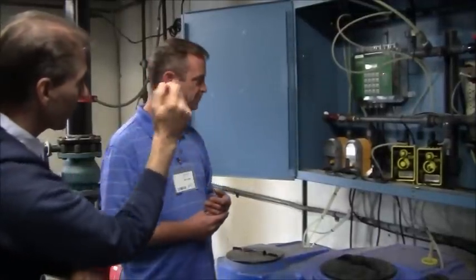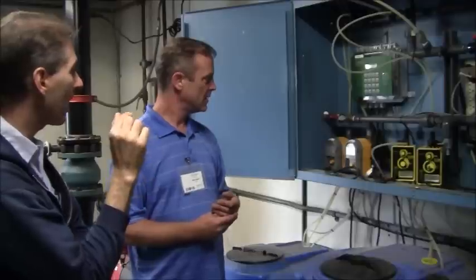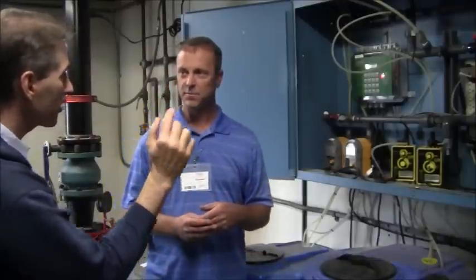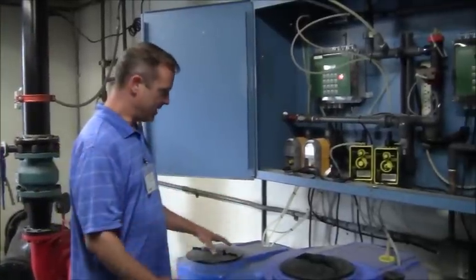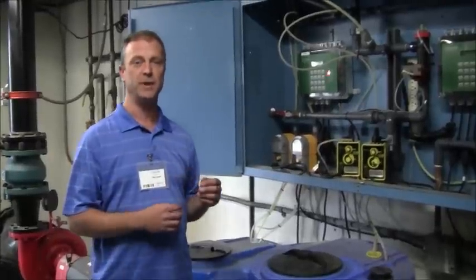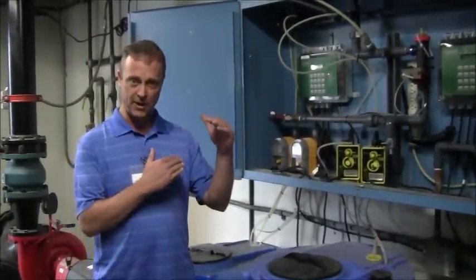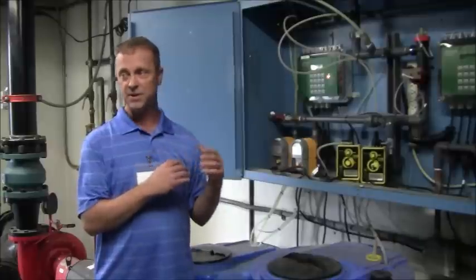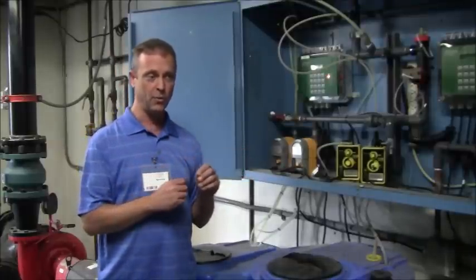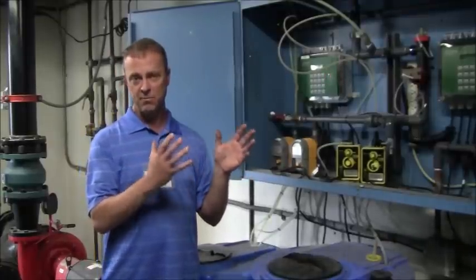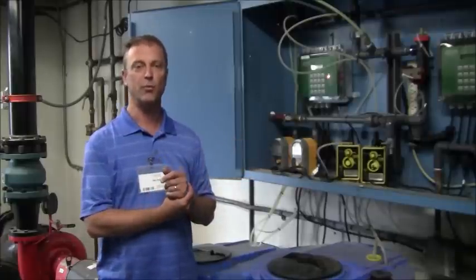That's correct. Now you said that the other pump over there was for a biocide. That's correct. Can you go into when we do the biocide treatment and how that works? Absolutely. In this particular instance, we're going to use bromine because the cooling tower is running at a cycled up level, so that means the pH is a little elevated. Anytime you get above a pH of 8.0 or so, you want to use a bromine product.